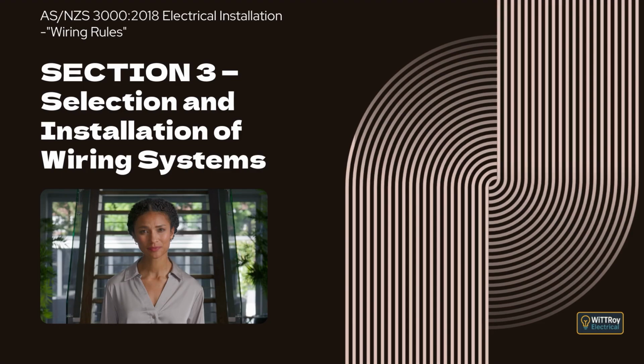Protection may be achieved by shielding, placing the wiring far enough away from the heat source, selecting a system that allows for extra temperature rise, limiting the current carried to reduce operating temperature, reinforcing or replacing insulation locally, or using another method that gives equivalent protection. Parts of cables or flexible cords within accessories, appliances, or luminaires must be suitable for the temperatures they will experience, or have extra insulation suited to those temperatures.